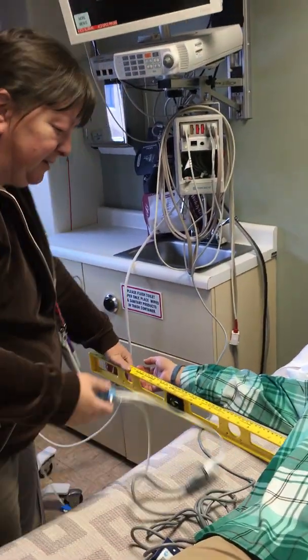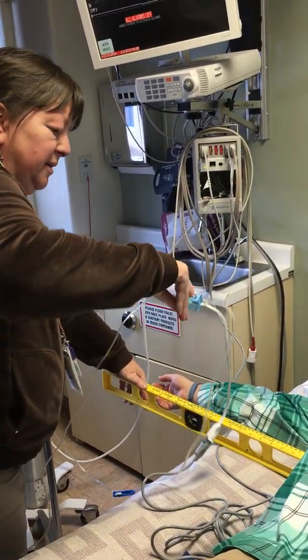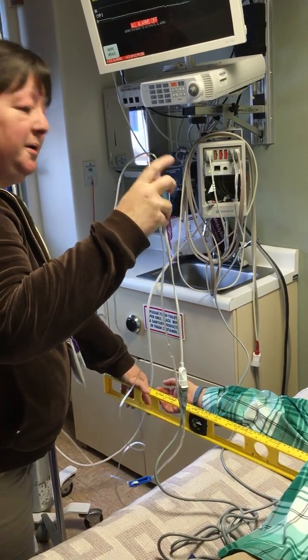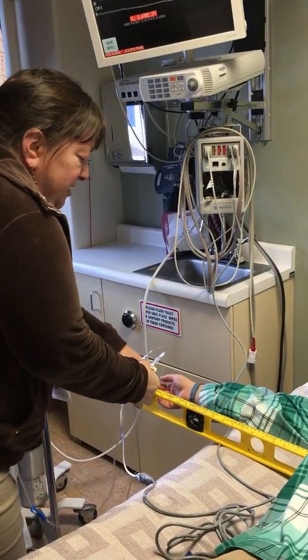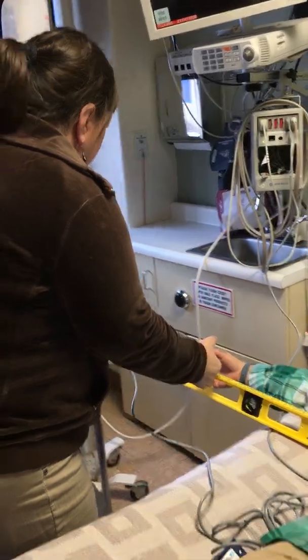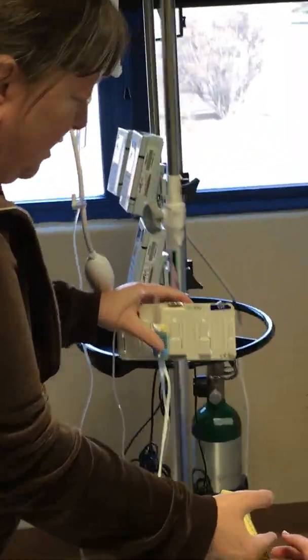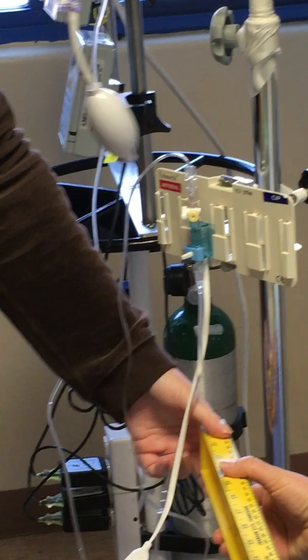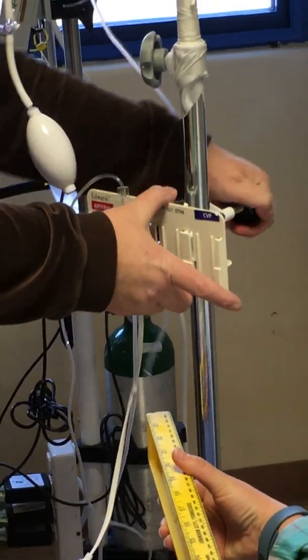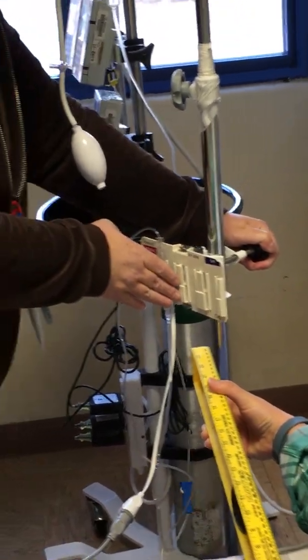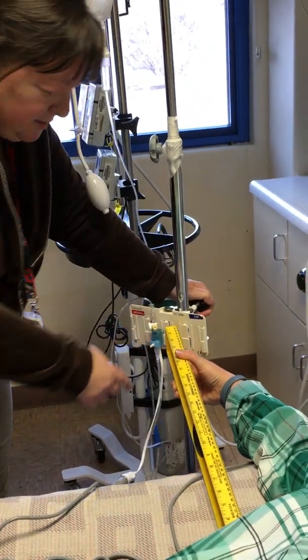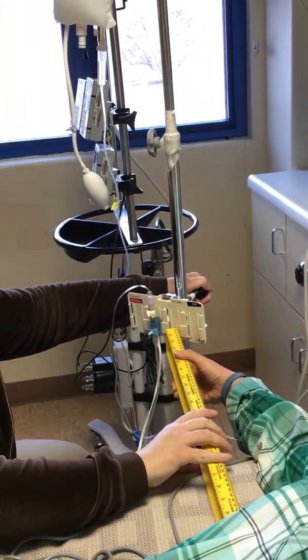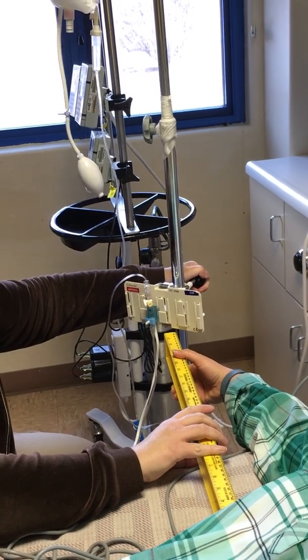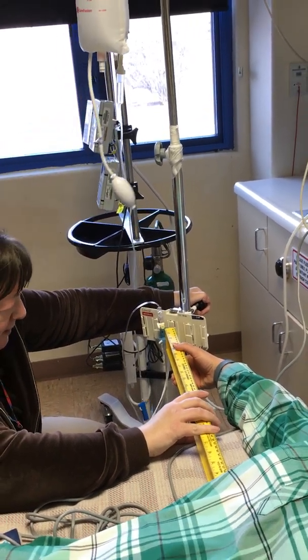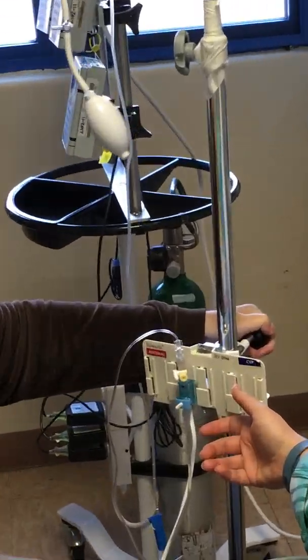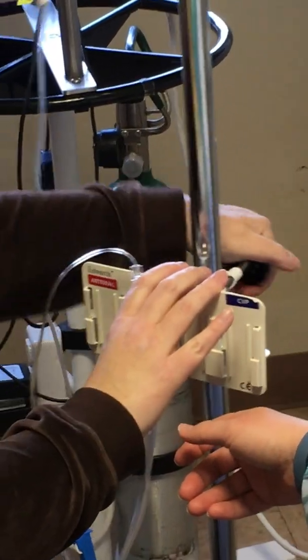So I'm going to put my level down. I'm going to put this with the hard part of the tubing up. The way I remember this is that the aortic arch is hard and it goes up, so the hard part goes up. And then, what's wrong with this picture? I'm not going to be level. So you want to get this part of the transducer level with the phlebostatic axis. Go down, look for your little bubble in the level, and this is right where I need to be. So now I can tighten my transducer and I'm ready to go.